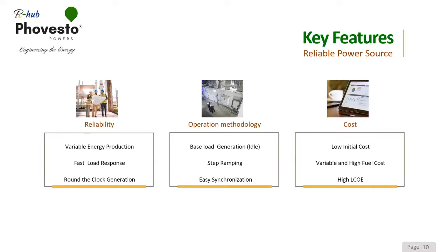The operation methodology for diesel generators is very simple. Since many attendees are from mechanical backgrounds, idling is a good reference point, we keep the engine at an idle state. That's the kind of generation needed to maintain a reliable power source, which cannot be turned off completely. It should run at a base load, usually around 30% of the plant capacity.